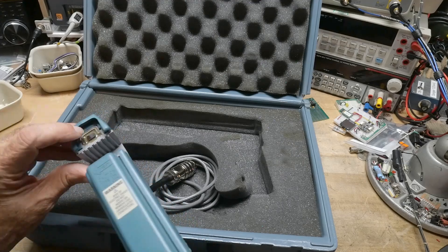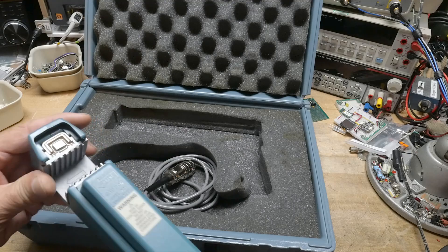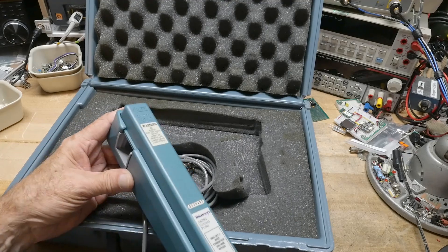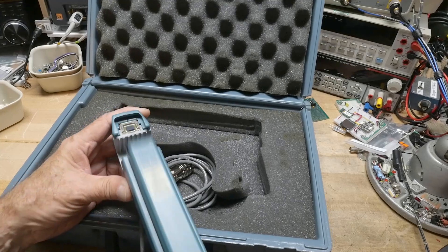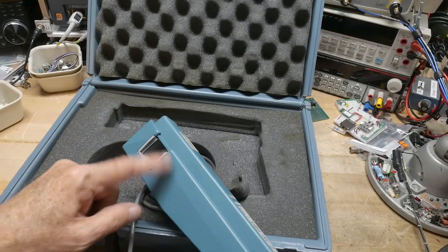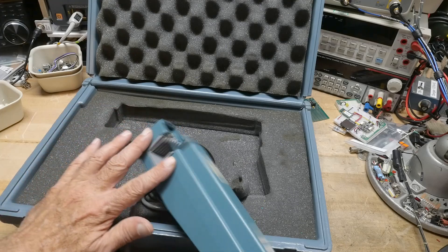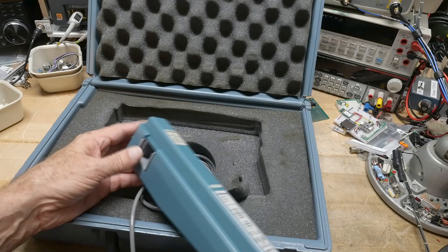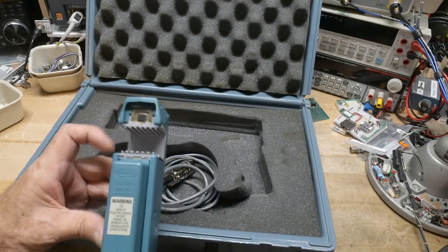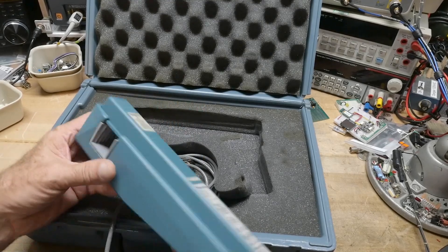I'm not sure if that's the Hall effect piece, but that looks like part of the sensor material. There's a loop here and coils — alternating coils on the two sides — and then it uses a Hall effect sensor to detect the amount of current. There's an arrow indicating the direction being detected.